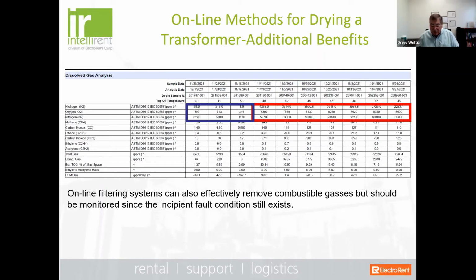We had a situation where a utility had ordered a new batch of, I think maybe half a dozen or so, auxiliary transformers for their power plant. And one of these transformers started to gas almost immediately as it was put into service. So they took it offline, they sent it back to the factory to be reworked. It had been reworked, and they put it back in service, and the gassing continued. And the gassing it was showing was hydrogen, oxygen, nitrogen, which really is an indication that you've got some kind of arcing and sparking going on inside the transformer itself, causing this condition.